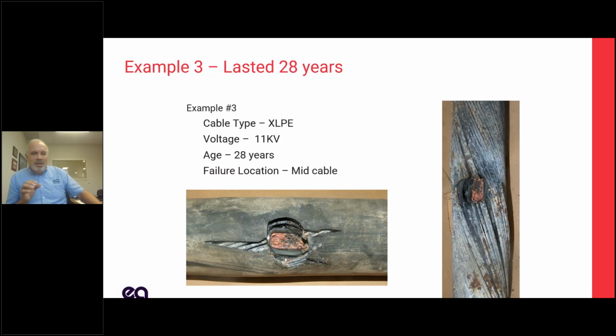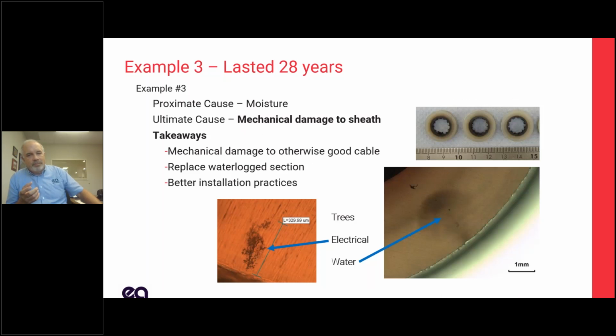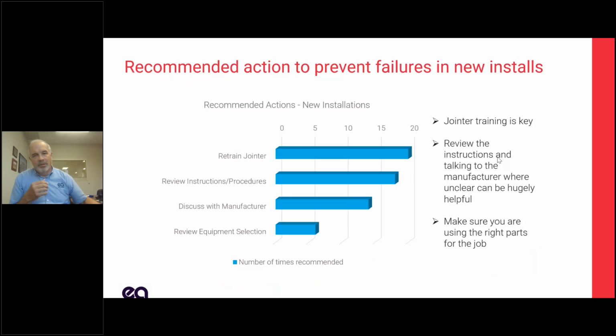Here's one that lasted quite a bit, 28 years. So this would be in our random midlife failure. It failed in mid-cable. Why did it fail? It failed due to moisture infiltration. When we look at it on an electron microscope, we see electrical trees, we see water trees. Water trees aren't so bad, but they tend to lead to electrical trees. This is good to know, because maybe I'm an asset owner and I've got 100 similar cables running in similar environments. I better plan on some more failures here. I'm not necessarily going to run out and replace them, but at least I know what this cause is. If I get any other mechanical damage, I could have a failure. So these sorts of things lead to the numbers that I showed above.